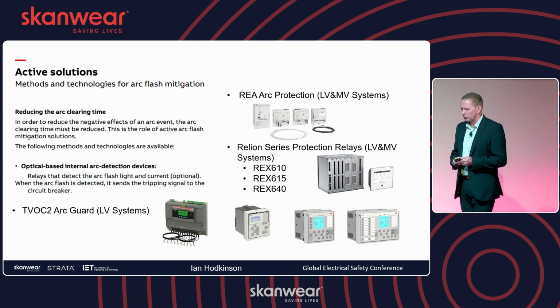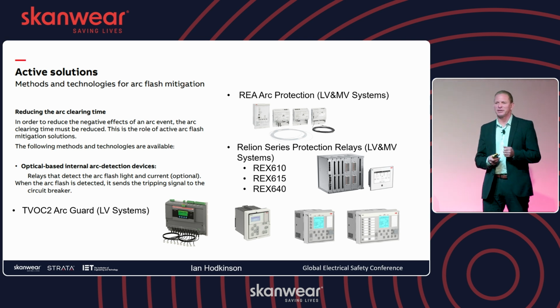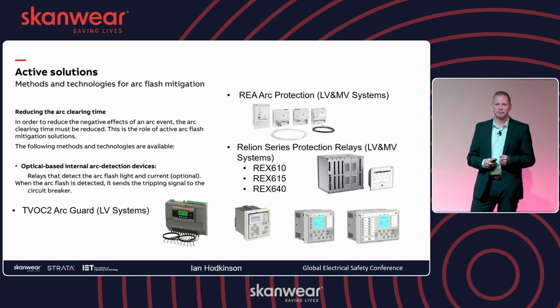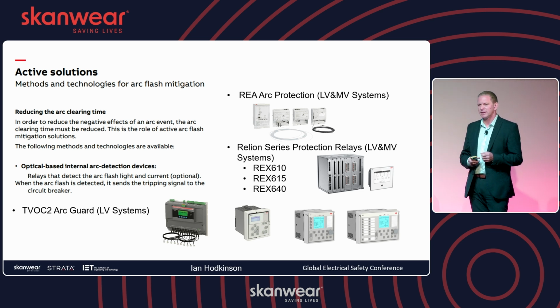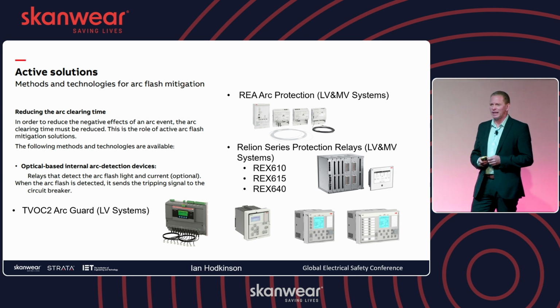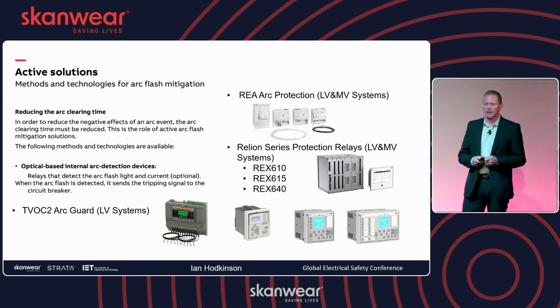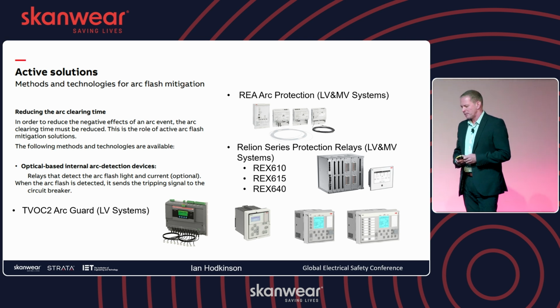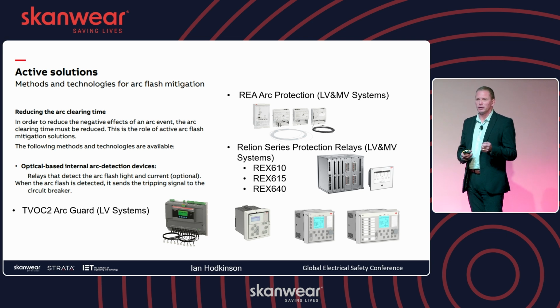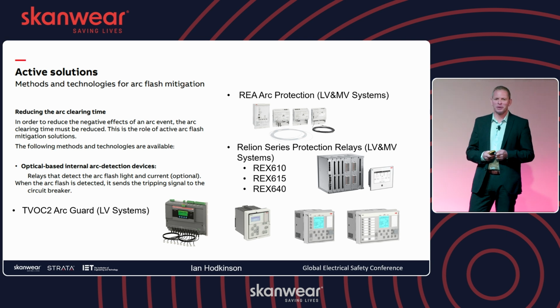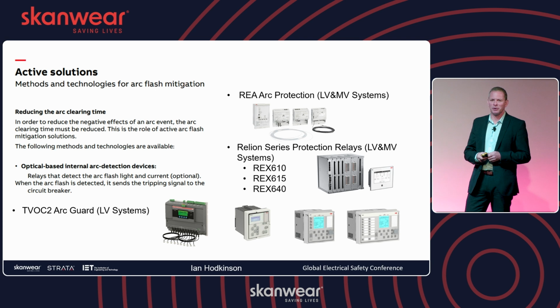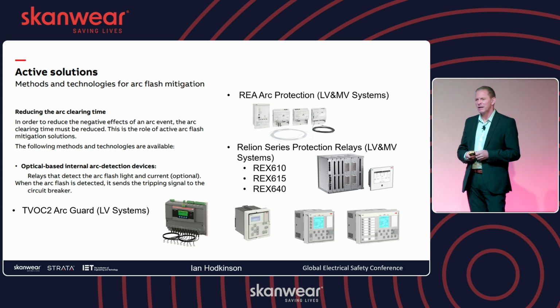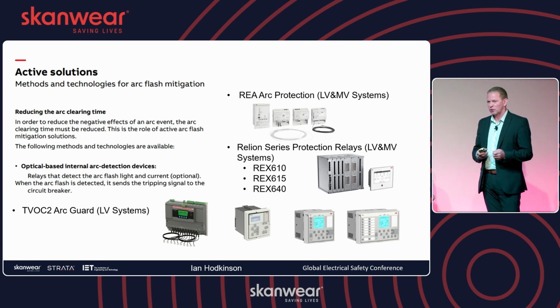Although it is quite important to say that the intensity of an arc light is completely different from just a normal daylight or torchlight. If you use a high intensity, in a lot of the devices you can set the intensity setting up to really high so that it will only be detecting an arc and nothing more. And always a good measure is that wherever you've got a light that's from an arc, if it is a genuine arc, you will guaranteed get a very high surge of current very shortly afterwards. So this current and light is always a good guarantee of detection.